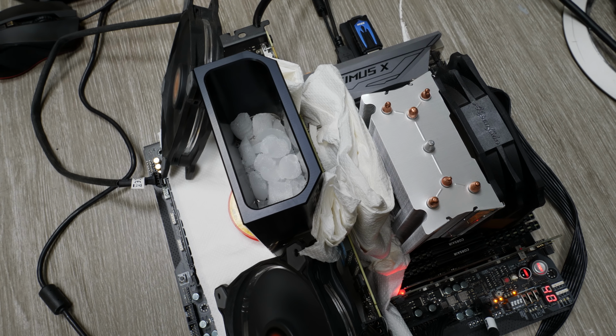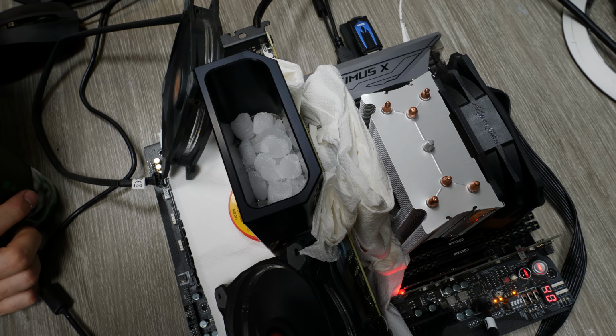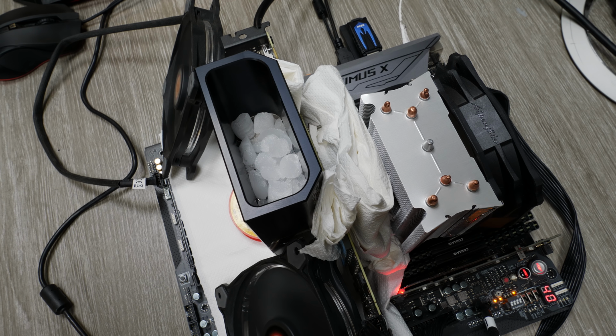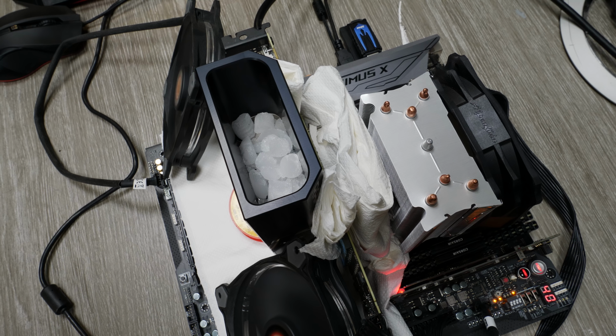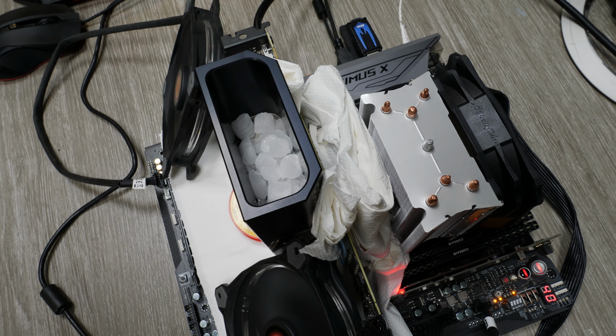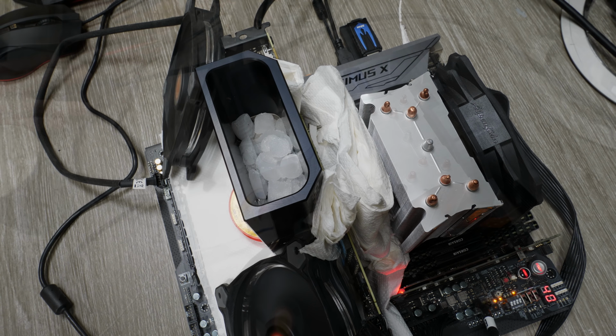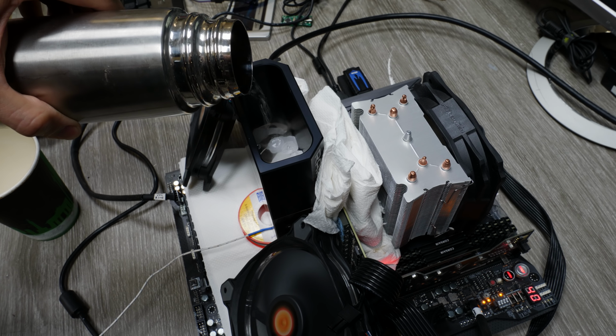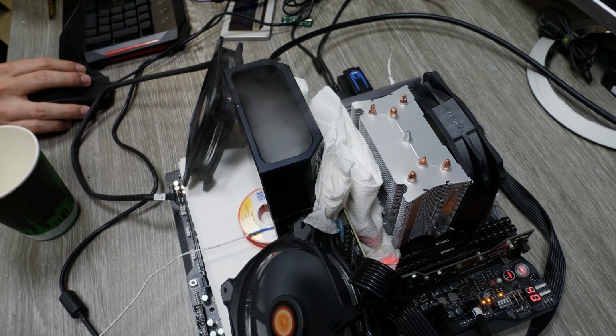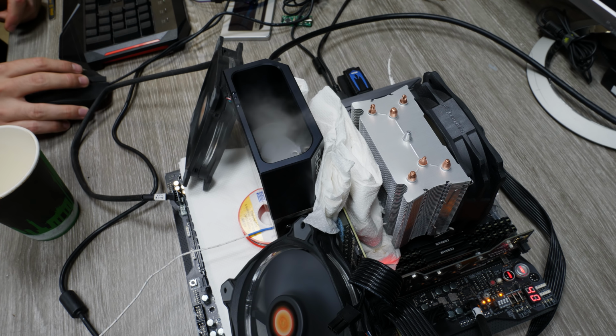Then we went full out, so we filled the GPU container completely with the dry ice nuggets and also added some 3M Novec for heat transfer. Typically we also add something like acetone or isopropanol. You can just take whatever alcohol you want, which has a very low melting point, but 3M Novec in addition is not electrically conductive, so if we spill something, it's more safe and it also doesn't smell as bad as acetone. So that's why we went for 3M Novec this time.